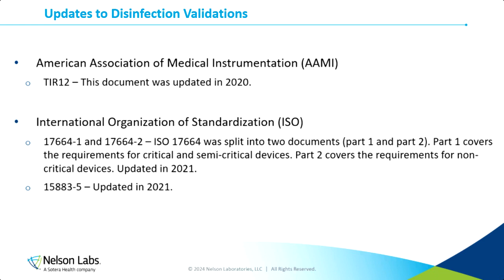The main document that was updated is the AAMI TIR12. This was updated in 2020, as well as ISO 17664, which was split into two documents, a part one and a part two. Part one covers the requirements for critical and semi-critical devices, and part two covers the requirements for non-critical devices. And then also ISO 15883-5, which was updated in 2021.